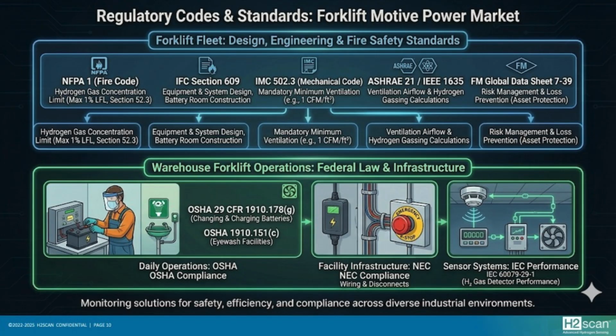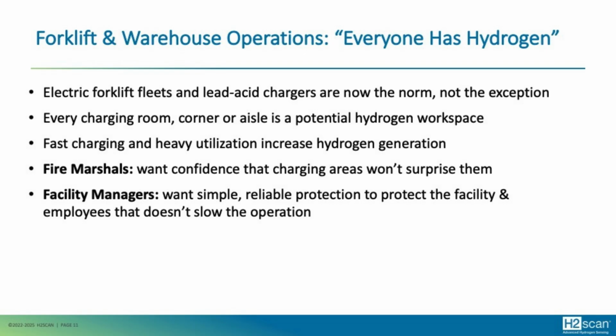So this is a graphic about all of the fire codes that you would have to consider with your forklift charging area. So you have NFPA 1, you also have the International Fire Code, the mechanical code for the ventilation fan, ASHRAE standards, as well as FM Global data sheets. All these play somewhat together in this space in making sure that you keep the proper ventilation and also keep hydrogen gas concentrations below 1%.